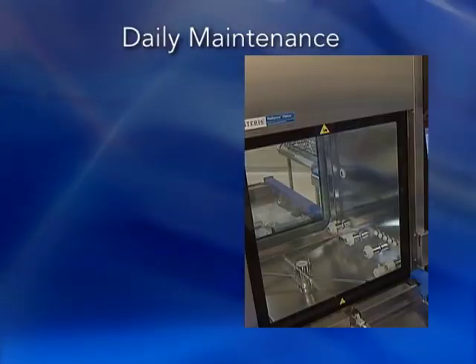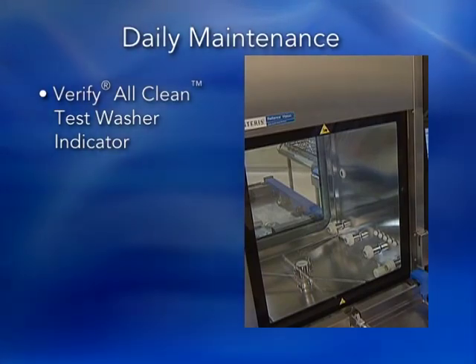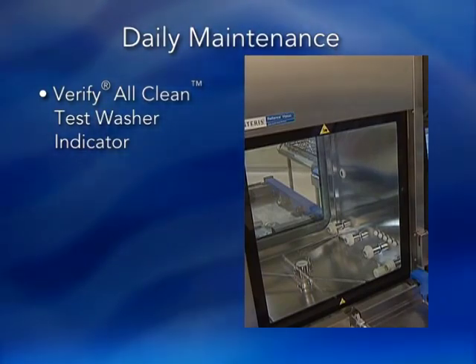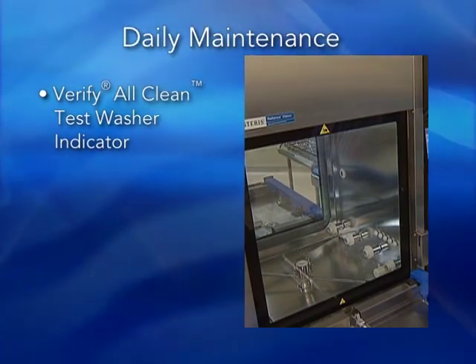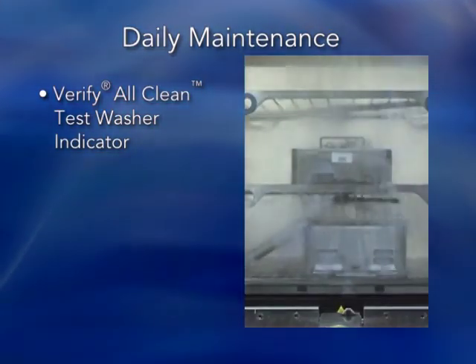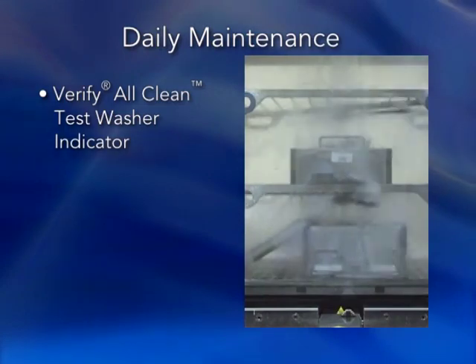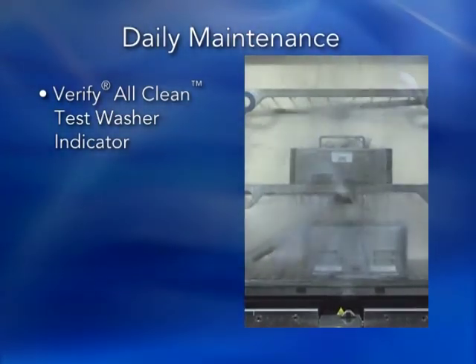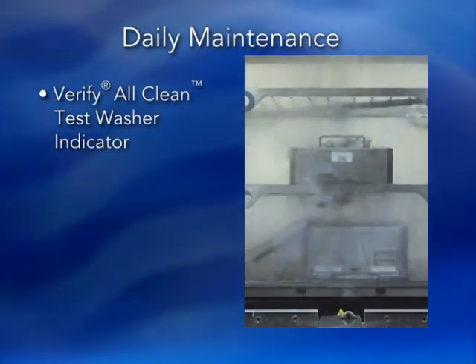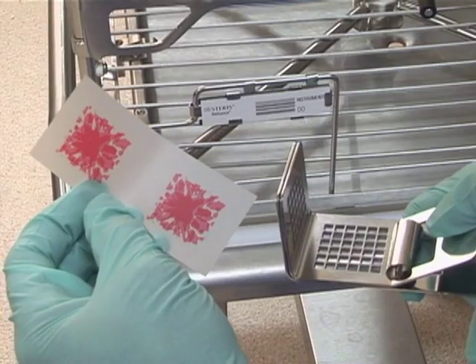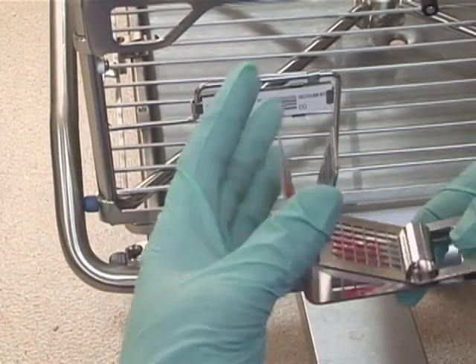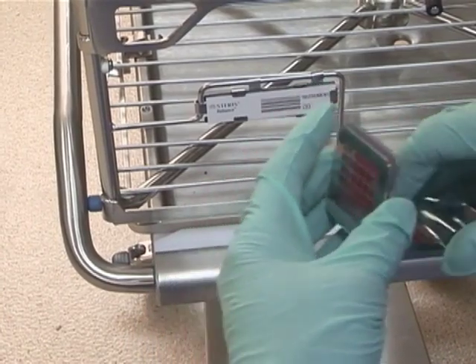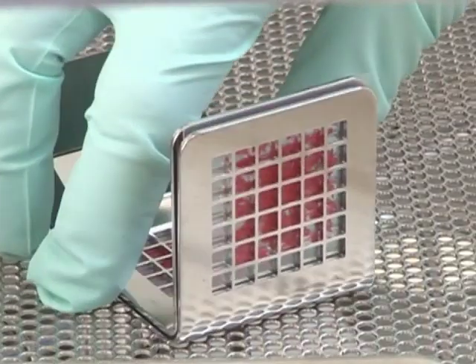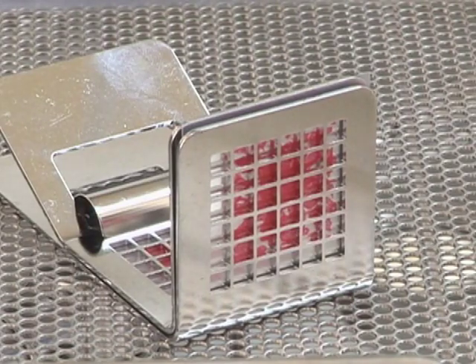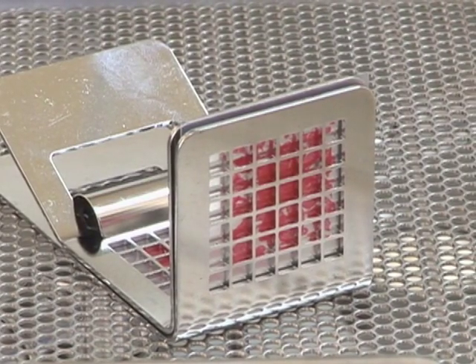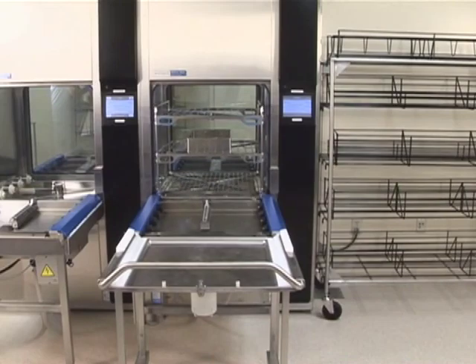The Verify All Clean Test Washer indicator is to be used in an empty instrument cycle to establish a control based on the level of assurance required. Once a control has been established, you can also run the All Clean Test indicator in a load with instrumentation and devices to provide an additional level of assurance. Place the indicator in the All Clean Washer indicator holder and then place the holder into a wire basket. Orient the holder as shown, with one of the soil stains flat on the wire basket and the other oriented vertically. Place the basket into a rack for processing.